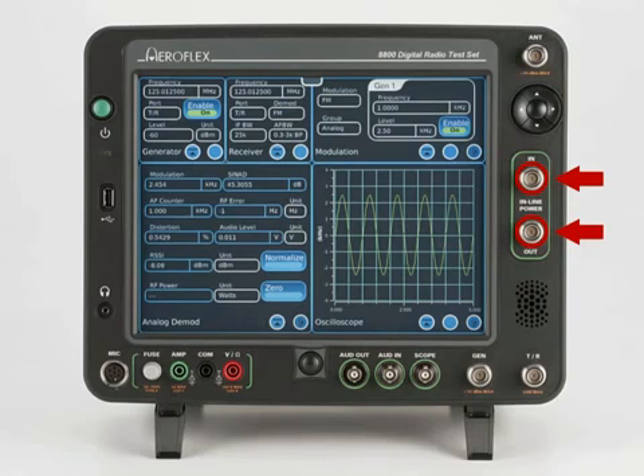The inline power meter provides simultaneous readings of forward power, reverse power, and VSWR. Its functions include average, peak, burst, crest, and CCDF power. The inline power meter is capable of measuring signal power up to 500 watts over a range of 25 MHz to 1 GHz to an accuracy of 4%. In other words, this portable unit is capable of measuring signals ranging from 500 watts down to minus 140 dBm.